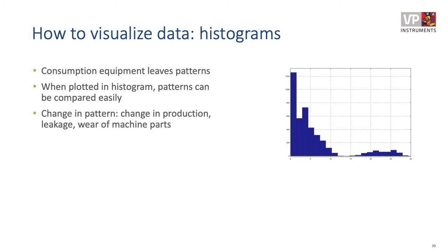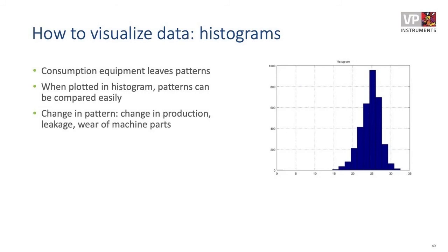So here's another histogram, and this is basically from a factory, by the way. In the first histogram, go back to the first one, you will see a lot of occurrences on the low side, and less flow on the high side. In this case, this was in summer when there was less production. And then on the next slide, you will see that the company is in full production, and they probably also repaired some leaks. And then you see the sweet spot is clearly pointed out, which is the most dominant air consumption of this plant.